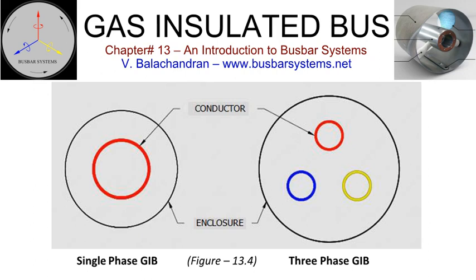Single-phase gas-insulated buses are more practical for the following reasons. Ease of manufacture. The electric field is radial and symmetrical if not uniform. It makes modeling and analysis easy. It is a very important criterion when designing a gas-insulated bus for high voltage, extra high voltage, and ultra high voltage systems. It eliminates phase-to-phase faults. The short circuit forces will be negligible not only because of larger phase spacing but because of the minimum flux design. The insulator span can be large, reducing the number of support insulators.